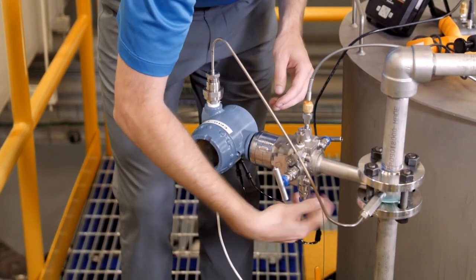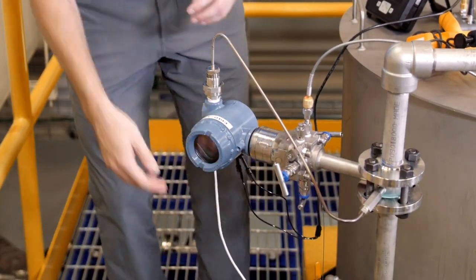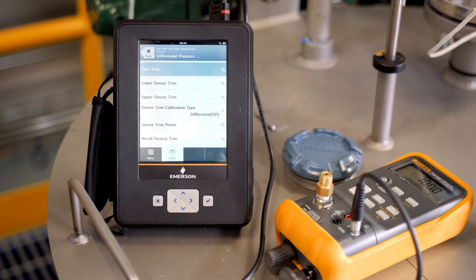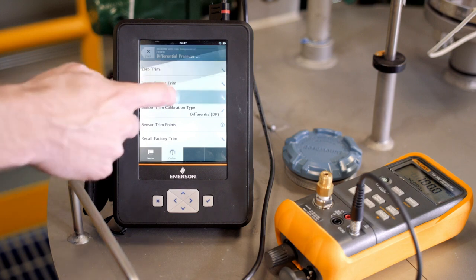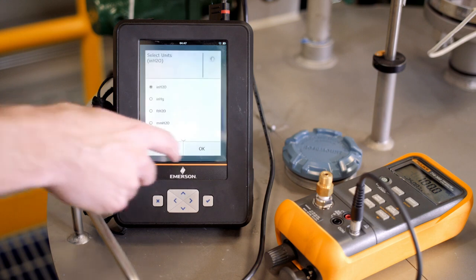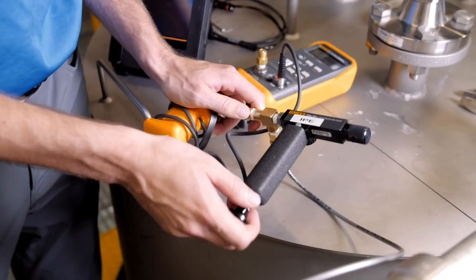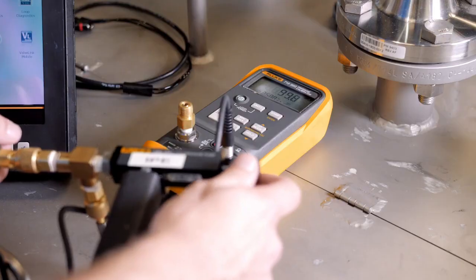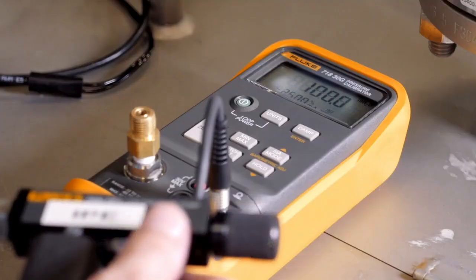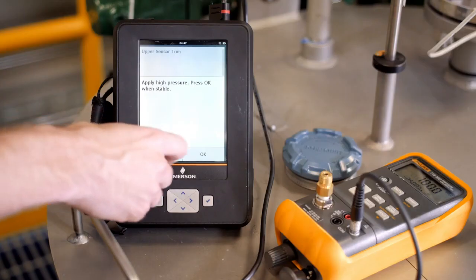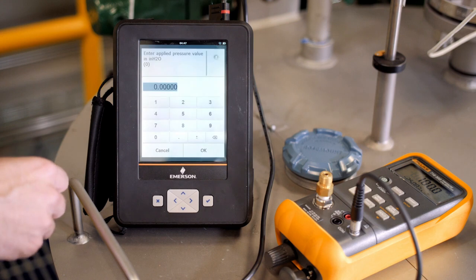The next step is to perform an upper sensor trim, which should be calibrated to the transmitter's upper operating limit. The valve should also be manipulated so that the high side is connected to a pressure source. Now select upper sensor trim. The first thing to choose is the units, and then we will apply pressure to the transmitter. For this example, we will apply 100 inches of water. Now enter that applied pressure on the Trex and follow the guided wizard to completion.